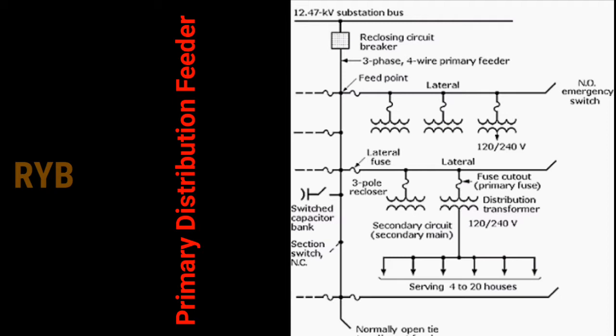In rural areas, a recloser is provided at specific locations in the feeder. A recloser is a device which provides automatic reclosing — unlike a circuit breaker, which opens the circuit but does not reclose automatically. A recloser is provided at various locations to remove the faulted section of the main feeder, and this is achieved through the coordination of all fuses and reclosers.